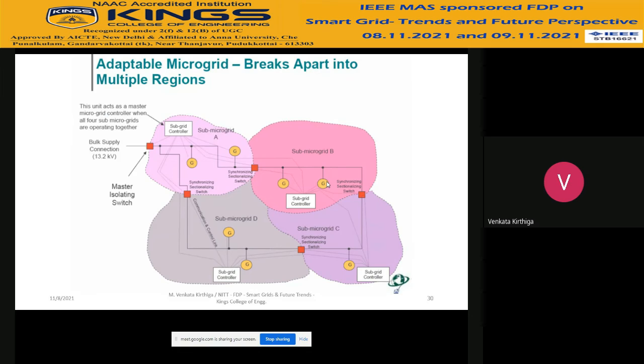In other words, if three sub-microgrids are having a problem and one is safe, to safeguard that particular microgrid, you can open the other two isolators, and you will have safe operation for that one microgrid. So it can happen either way - you can remove a microgrid where there is a problem, or protect a small portion of a microgrid that doesn't have a problem. Once the main problem is resolved, you can connect it back, but you have to be very careful about the restoration activities.